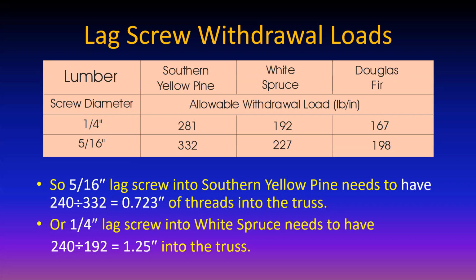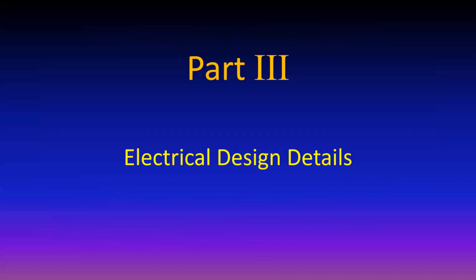And all the designs we have here, for any typical kind of roof, whether it's a tile roof or a shingle roof with trusses and residential type design, pretty much all of them just come out specifying 4-inch lag screws that get through the thicknesses of the mounting feet and the roof decking and down into the truss, and it very much exceeds the 3/4-inch penetration. Typically, it's 2 to 3 inches. So pretty straightforward stuff. Even an electrical engineer can figure this kind of stuff out. And we're going to show here now how mechanical engineers can figure out the electrical design details.